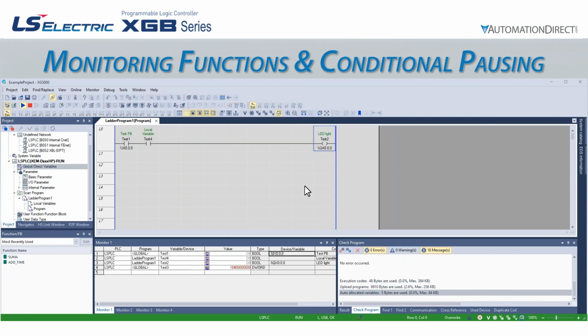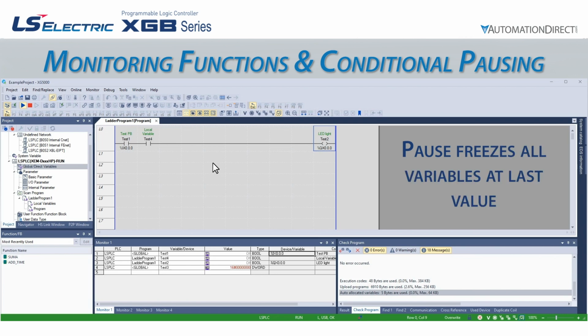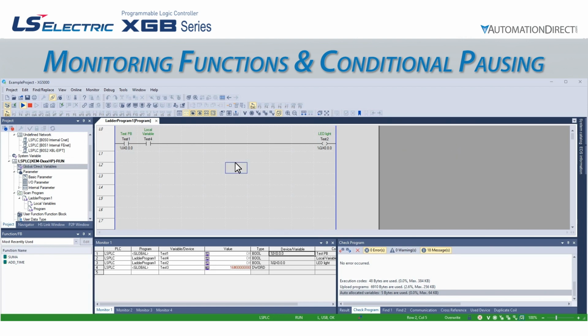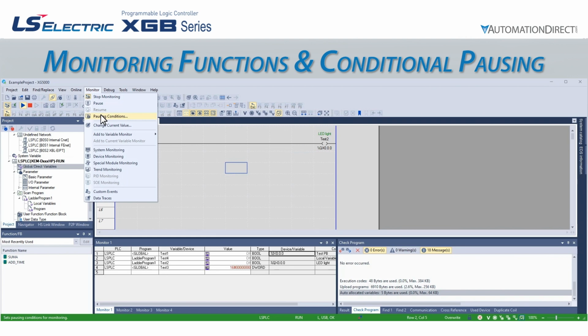Often, when logic is executing, several variables might trigger the same action or activity on the part of the PLC. This can make confirmation of which variable actually triggered the action difficult to trace. To address this, the XG5000 software has the ability to pause the software monitoring based on a preset condition or conditions. When the monitoring pauses, all variable values will be frozen in the software, but the CPU will continue functioning normally.